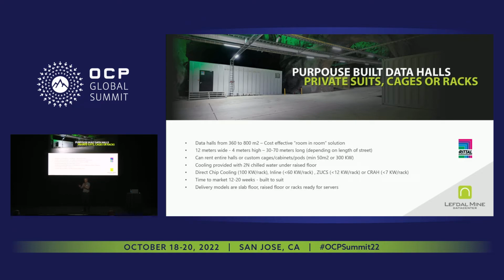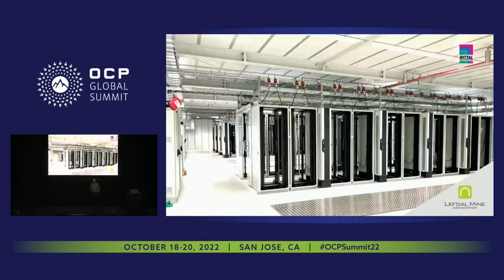It's a modular system made of wall elements, ceiling elements, and floor elements, all tested as a system according to European norms when it comes to fire rating, burglary protection, intrusion, IP rating, etc. It's also built in a modular 60 centimeter step, and we can build up to 800 or 1,000 square meters of these facilities. We can include every type of cooling solution already discussed - direct-to-chip, inline, or room cooling facilities. It takes a little bit longer time to market, as we have to assemble these units on site after pre-installing and pre-manufacturing them in one of our production sites.